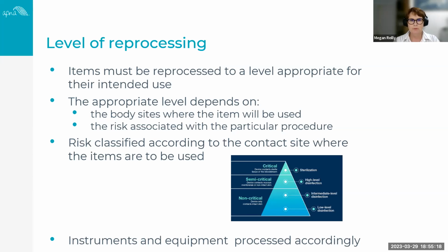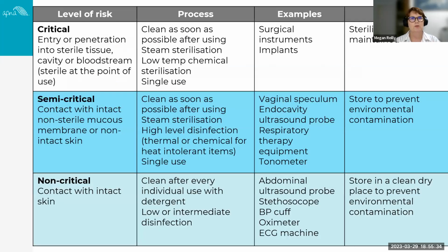So reprocessing really begins with processing at the point of use, in other words, in close proximity to the point of use, where it facilitates the subsequent cleaning steps. That's what we will be working through today. This slide shows you the level of risk in relation to critical, semi-critical and non-critical devices, and the level to which we need to reprocess that item.